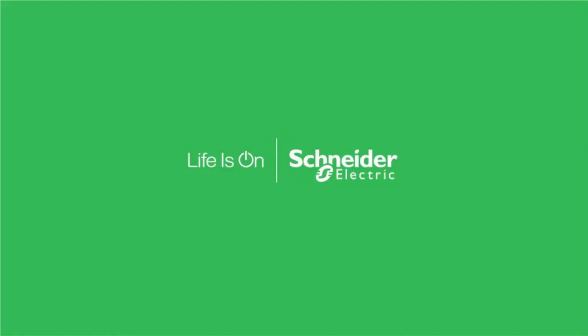The every 5 years thing, we've been in facilities where every 5 years we go back and revalidate things and really find that not much has changed. And so it may be just a process of looking at the previous results and saying, okay, these are still valid. In other cases, we find that the utility has upgraded their lines, or maybe they've had to change out a transformer because load is growing. They're adding additional process equipment in their facility, and so levels need to get updated. Those are the guidelines in 70E that either when major changes are made or at least reassess it every 5 years.